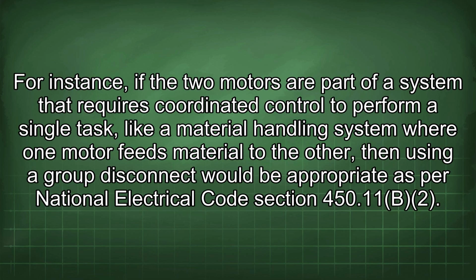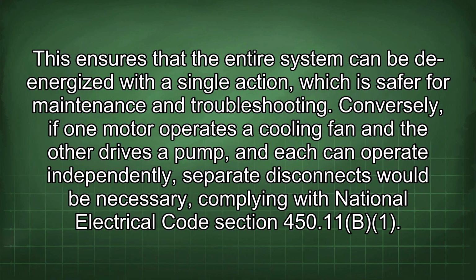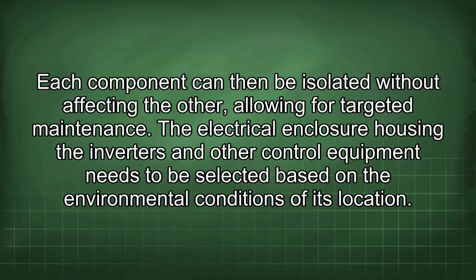For instance, if the two motors are part of a system that requires coordinated control to perform a single task, like a material handling system where one motor feeds material to the other, then using a group disconnect would be appropriate as per National Electrical Code section 450.11b2. This ensures that the entire system can be de-energized with a single action, which is safer for maintenance and troubleshooting. Conversely, if one motor operates a cooling fan and the other drives a pump, and each can operate independently, separate disconnects would be necessary, complying with National Electrical Code section 450.11(b)(1). Each component can then be isolated without affecting the other, allowing for targeted maintenance.